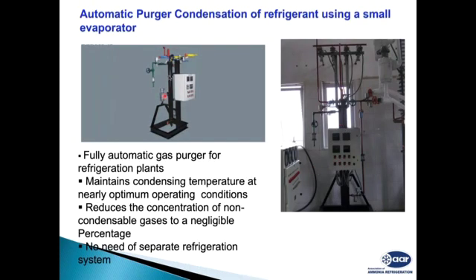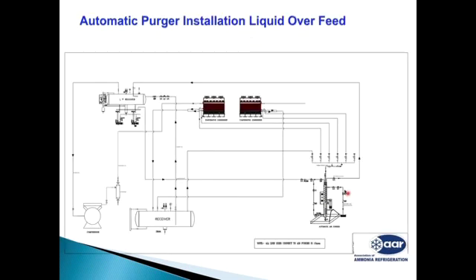Second one, this is a photograph of a purger which is running using a refrigeration system, an in-house refrigeration system. Typically, these drawings show the purge points taken from the outlet of the condensers. A multi-point purger can be used in a big system if you have multiple condensers and receivers. This is another purge point coming from the receiver, and liquid is fed through this LP vessel, pump vessel system. Liquid is fed here and it goes back into the LP vessel. So whatever liquid comes in cools the coil inside the purger, and these foul gases are connected one by one to the purger.